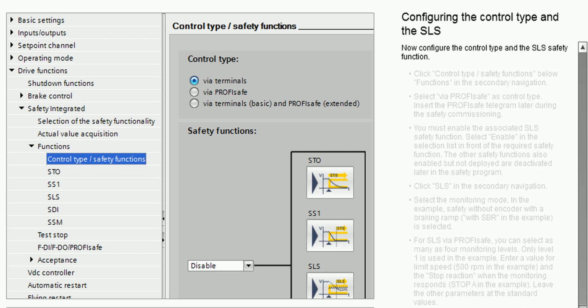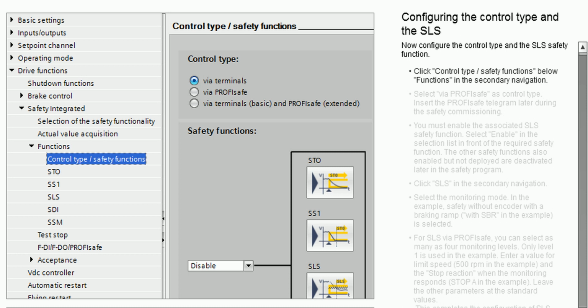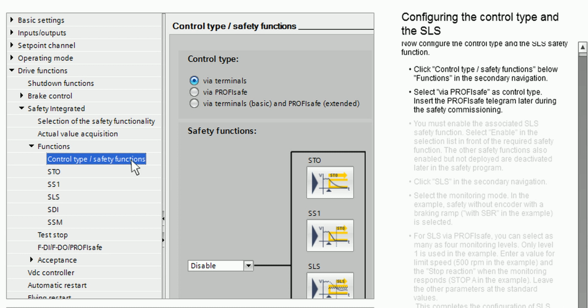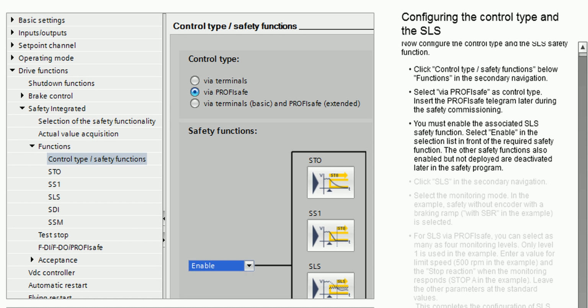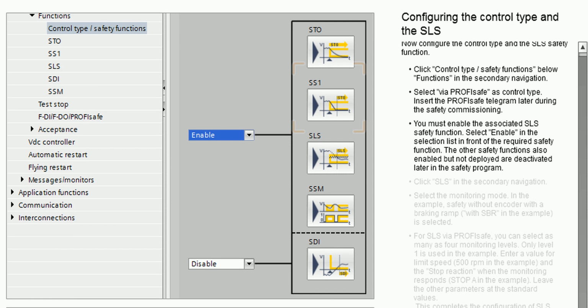Now configure the control type and the SLS safety function. Click Control Type, Safety Functions, below Functions, in the secondary navigation. Select PROFIsafe as control type. Insert the PROFIsafe telegram later during the safety commissioning. You must enable the associated SLS safety function. Select Enable in the selection list in front of the required safety function. The other safety functions that are also enabled but not deployed are deactivated later in the safety program. Click SLS in the secondary navigation.